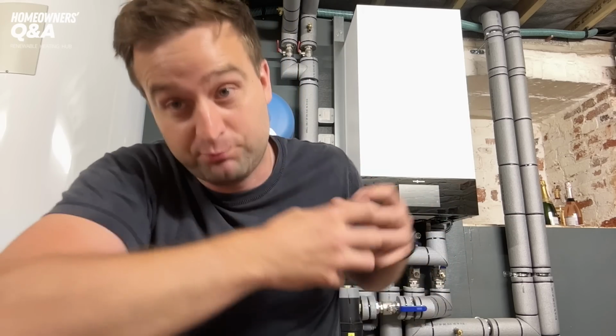Because it is emitting the heat into the room, it feels cold. And that's why it feels cold. It's not because the heat has not got there. There's just not enough heat to heat that radiator up properly because it has emitted that heat into the room already. Temperature and heat are two different things, aren't they? Altogether different things. Because the heat is the energy that's taken to the radiator through flow, which is why you need the right pipe sizing. The temperature is one thing, but the heat is the amount of energy that goes there. It's a slightly different concept.